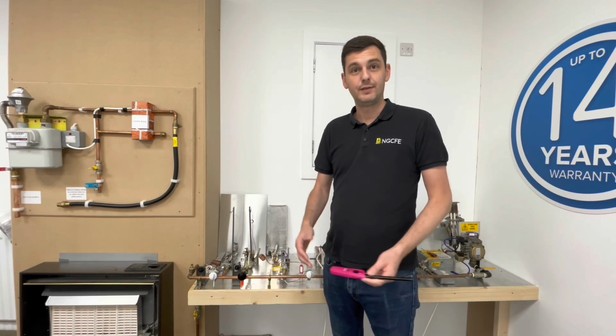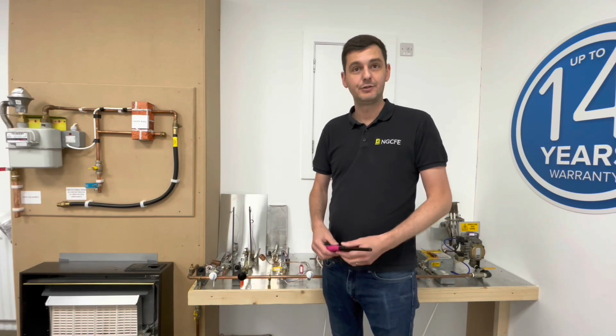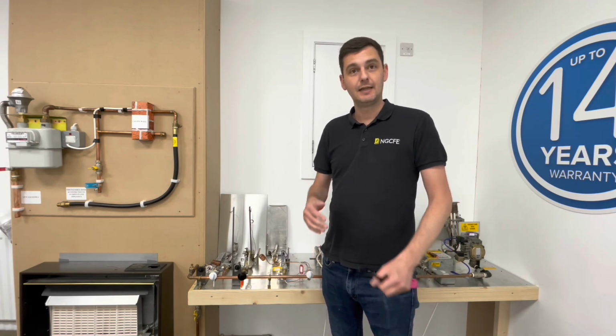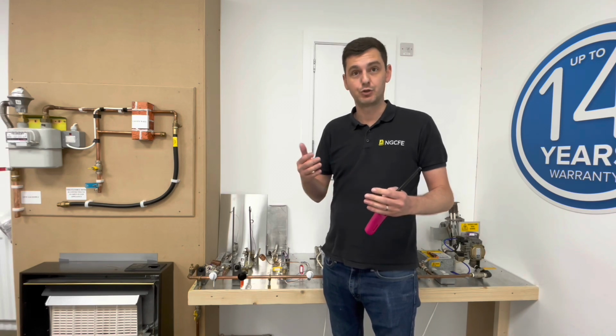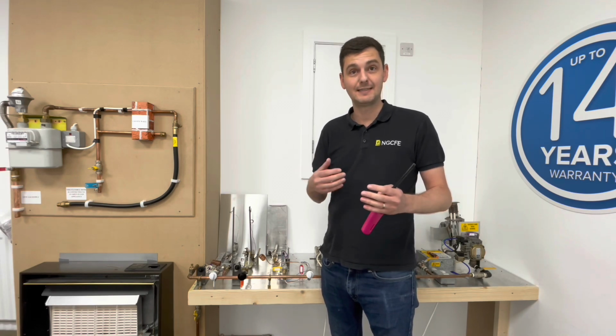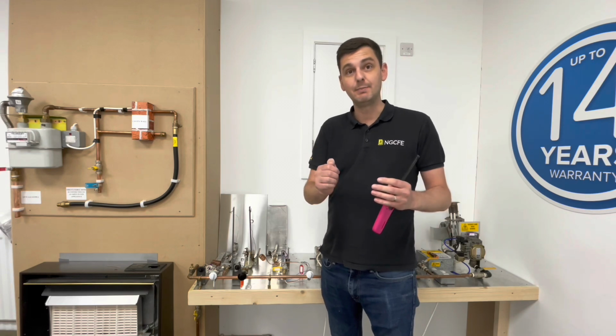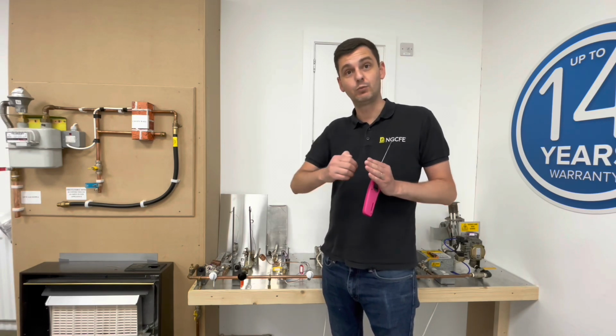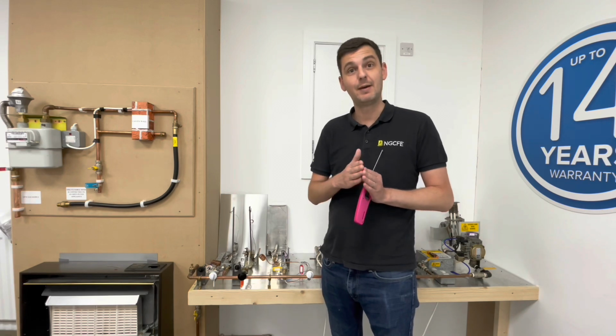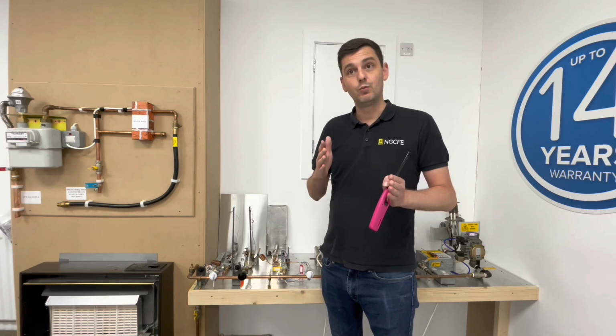Thermoelectric valve with interrupter, or interruptible thermoelectric valve. We've already spoken about thermoelectric valves and how they work. You'll have a thermocouple, which is then engulfed by a flame or a pilot light. That will then heat up and create a small current or a small voltage that will then hold open a magnetic valve. So when we manually open the valve first, and then once the thermocouple is heated up sufficiently, the voltage and the current that it produces will hold the valve open via a magnet. Now, what we haven't discussed is how we can introduce interrupters into that.